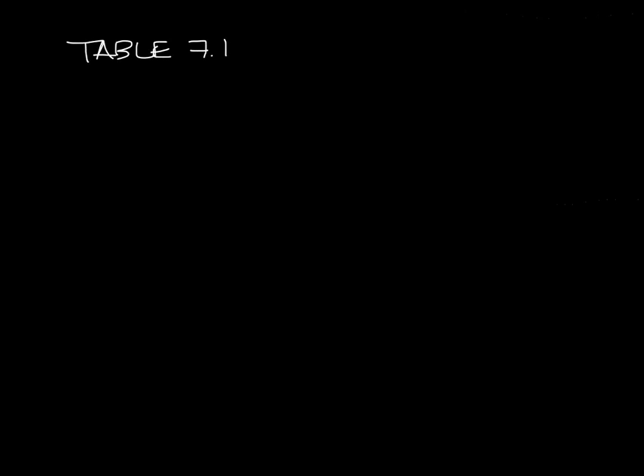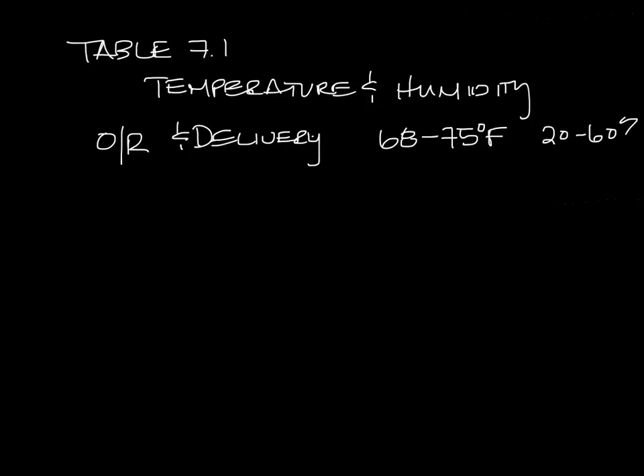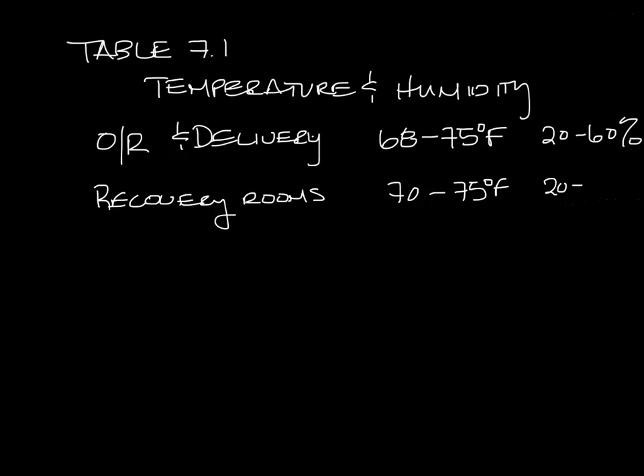Table 7.1 also shows the design temperature and relative humidity ranges for each type of space. For instance, operating rooms and delivery rooms are supposed to be 68 to 75 degrees and 20 to 60 percent relative humidity, whereas recovery rooms can be 70 to 75 degrees and 20 to 60 percent humidity.